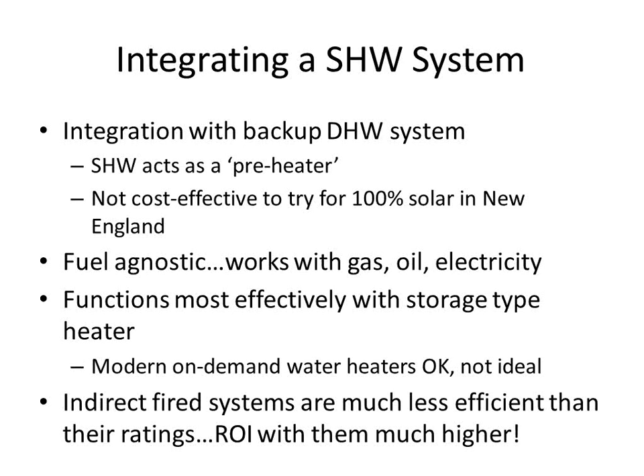What that means is that indirect fired systems benefit much more from the solar hot water system than the traditional calculations will tell you. Because if you start plugging in the typical efficiencies for these boilers, they're going to give you a savings, an offset. But really, you're offsetting a lot more because these systems are just so much less efficient in the summertime than the numbers indicate.